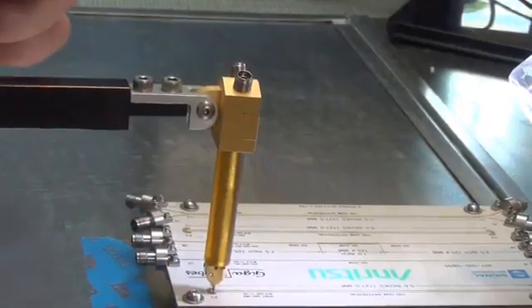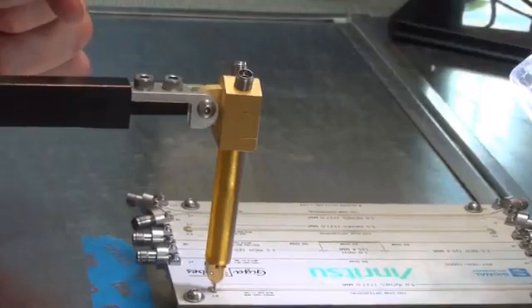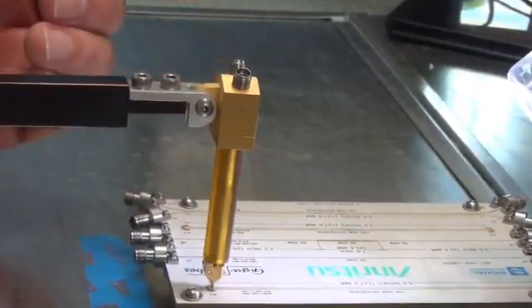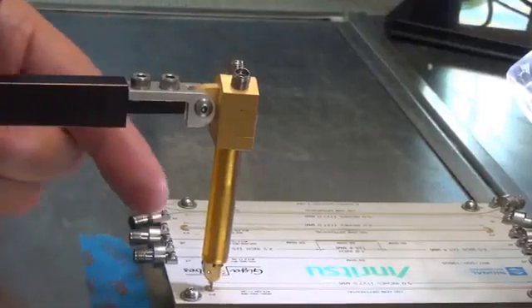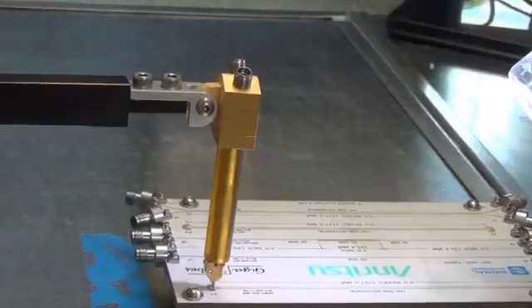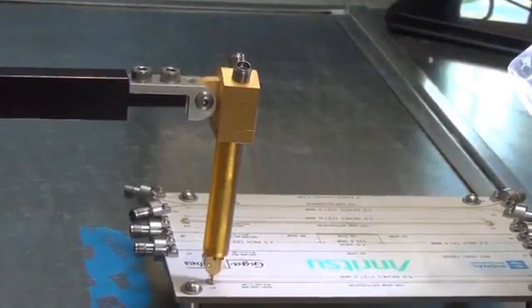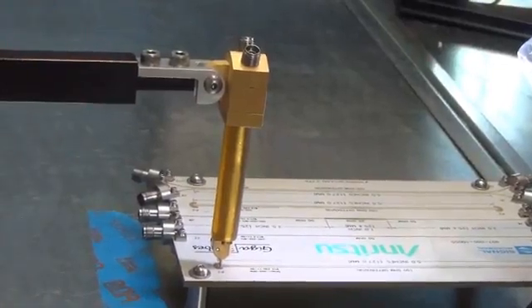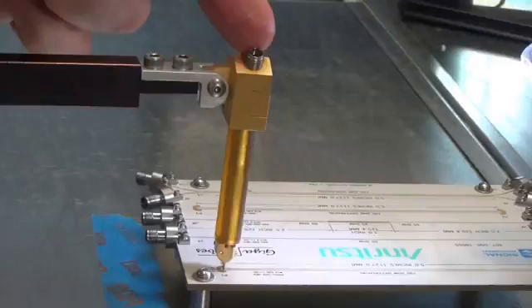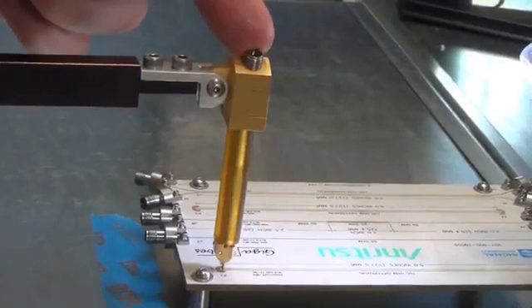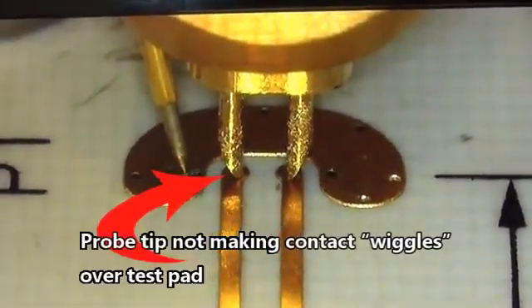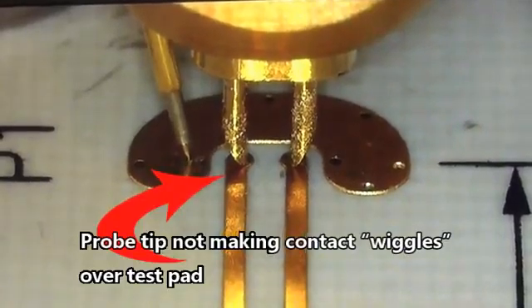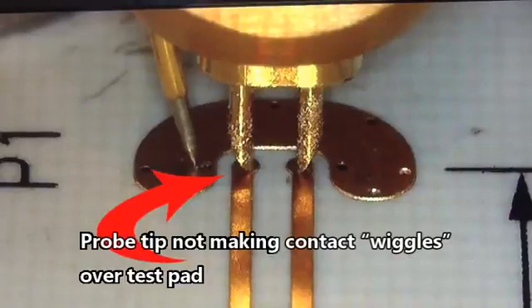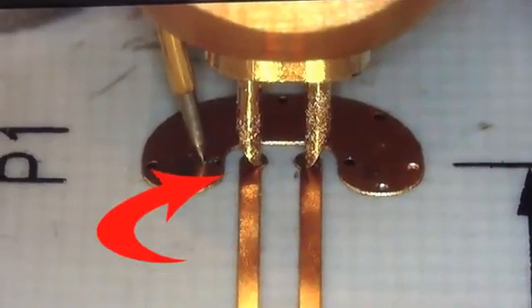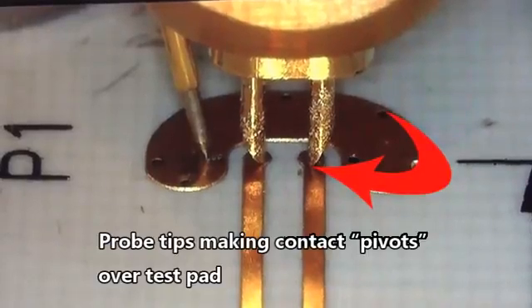Okay, now that we've adjusted our probe to put it on the test pads, what we want to do is verify that both probe tips are making contact with the test pads. One little trick I've found effective at determining whether they're planar is I just put my finger a little bit behind the two differential connectors, and I wiggle my finger back and forth, and I watch the probes in the display. If the probe isn't making contact, it wiggles back and forth. The other one will pivot back and forth. The one that's wiggling is not making contact, nor will it be making electrical contact.